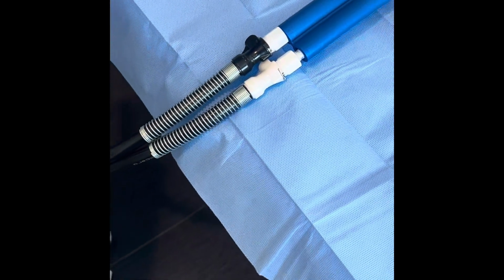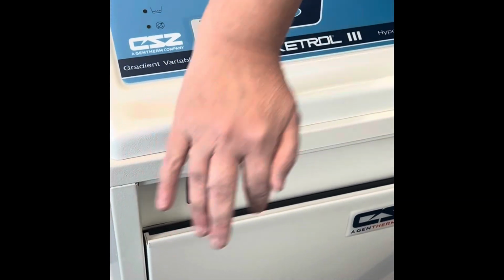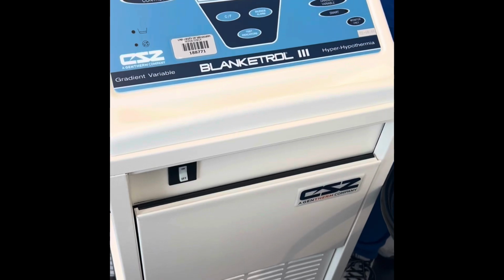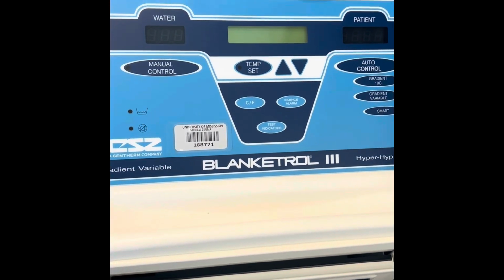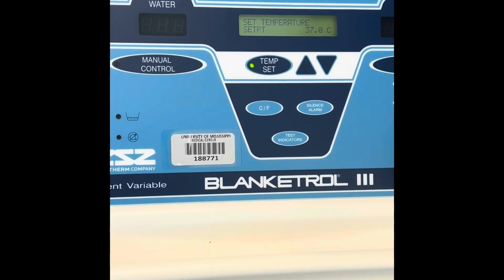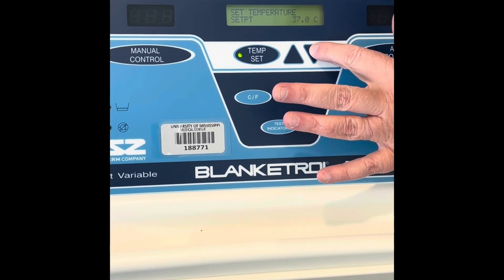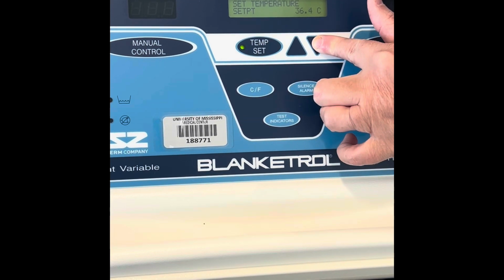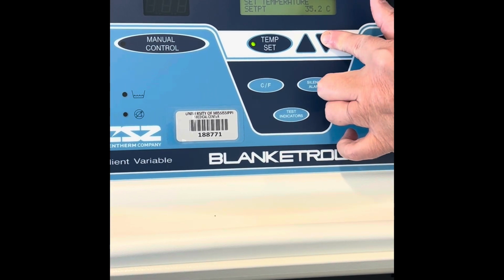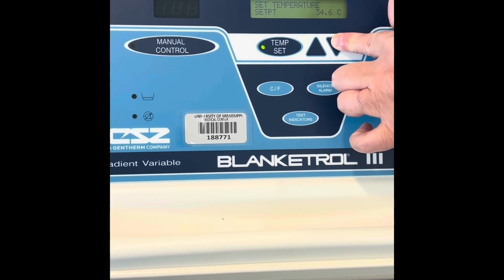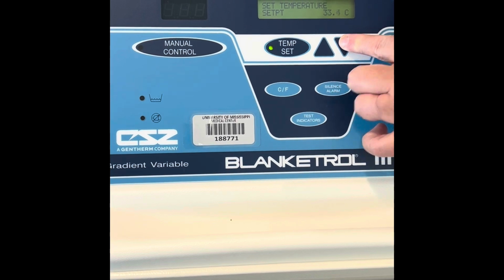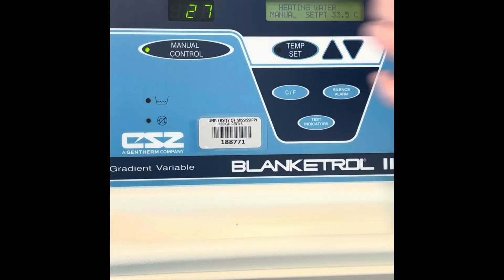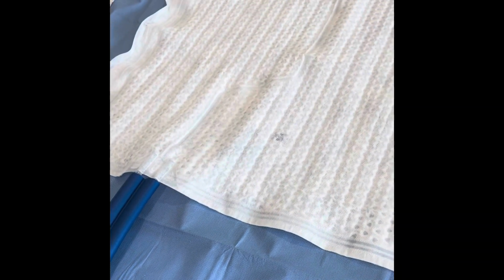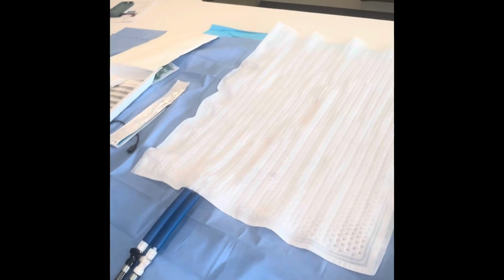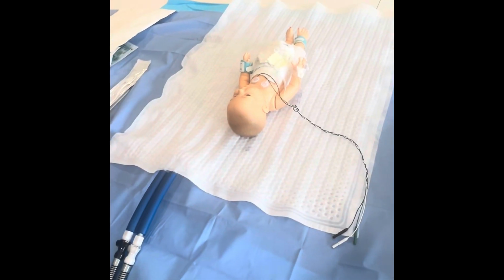Plug in the machine and turn the power switch to on. Operate the machine in manual mode until your infant arrives and is placed on the cooling blanket. Set your temperature to 33.5 and then ensure that you are in manual mode. Prepare your infant for cooling. Ensure all connections are secure.